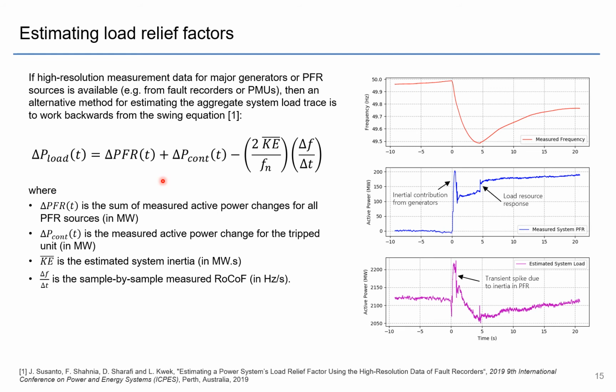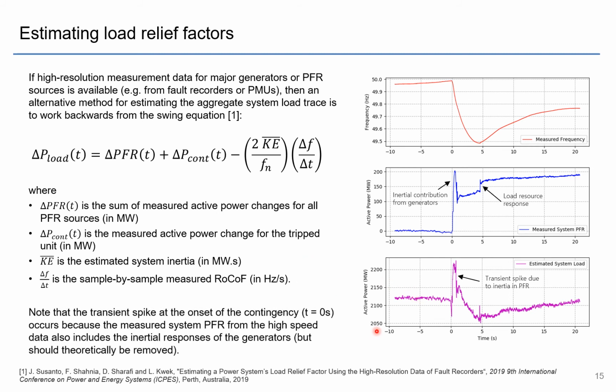This is an example from the Swiss system. This was a frequency trace after the contingency. This was the PFR during the contingency, and you can see there was also some load response. This is a load resource that tripped off on under frequency relay, and here you can see the load trace after using this method. There are some spikes here, and the reason for this transient spike in the load is that we're including inertia in the PFR, but in the swing equation, inertia is endogenous to the model. It's already built into this KE value, so strictly speaking, we should have removed that section. But in any case, you do get a better alignment between the frequency trace and the load traces for you to calculate the load relief factor.